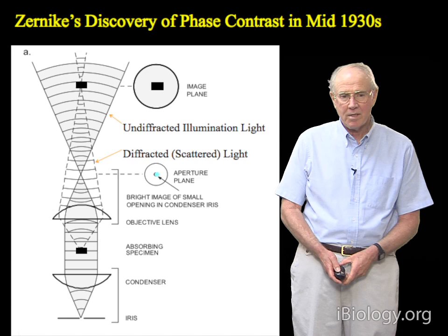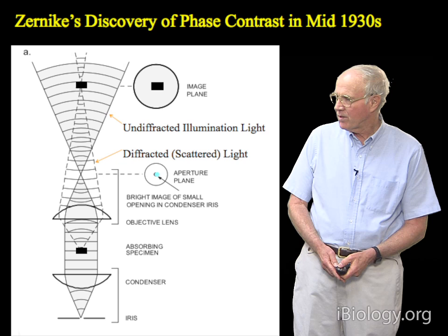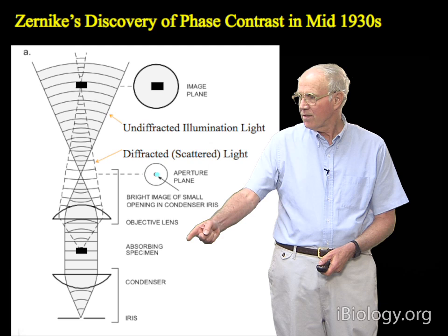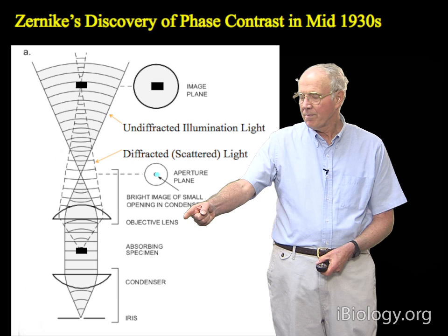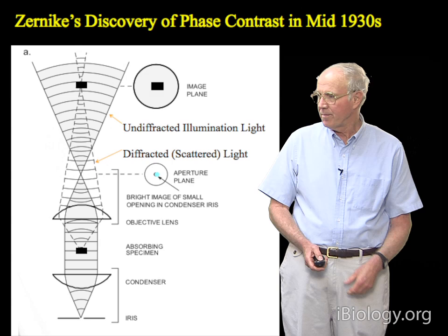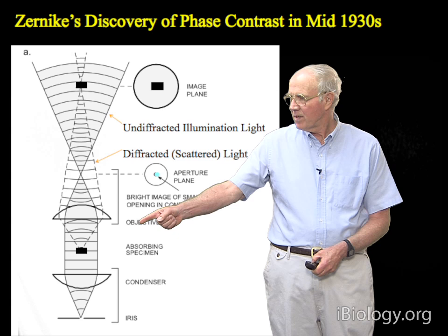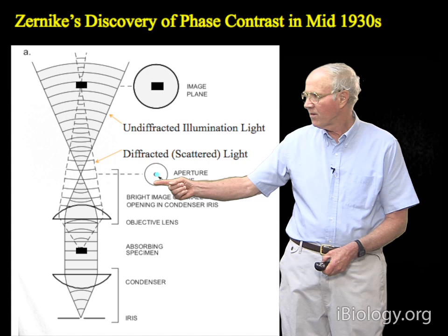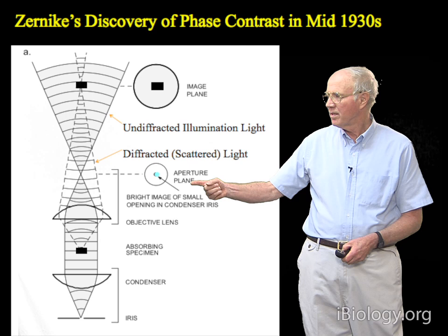The setup of the microscope he used in these experiments is shown in the diagram here. It's set up for Köhler illumination with the following adjustments: the iris diaphragm on the condenser is closed down to a very small spot, and as a result, that illuminates through the condenser and produces a beam of plane wave illumination of the specimen. The specimen he initially used was very fine carbon particles sprinkled on the surface of a coverslip mounted onto a glass slide. When the plane wave hits these fine carbon particles, a lot of the illuminating light just passes by and is collected by the objective lens, then becomes focused at the objective back focal plane — also called the back aperture — as a point.